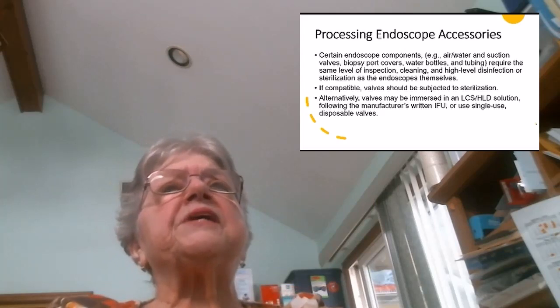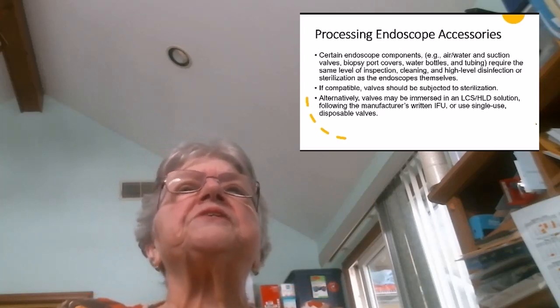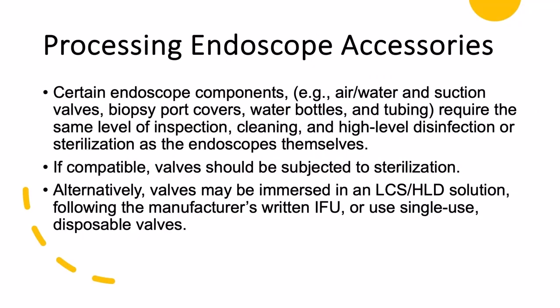We talked about the accessories. Make sure that all of the accessories, such as water bottles and tubing, are processed according to the IFU. And we talked about the valves, making sure that they were subjected to sterilization or according to the IFU. Any accessories that break the mucosal barrier should be cleaned according to the IFU and sterilized between each patient. You should not do high-level disinfection.